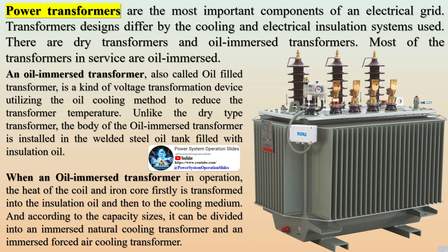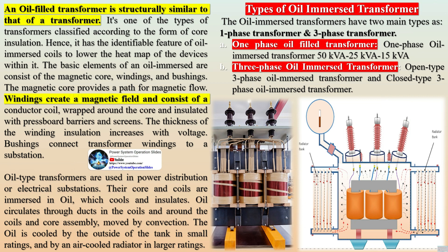An oil-immersed transformer, also called an oil-filled transformer, is a kind of voltage transformation device utilizing the oil cooling method to reduce the transformer temperature. Unlike the dry-type transformer, the body of the oil-immersed transformer is installed in a welded steel oil tank filled with insulation oil. When an oil-immersed transformer is in operation, the heat of the coil and iron core is first transferred into the insulation oil and then to the cooling medium. According to capacity sizes, it can be divided into an immersed natural cooling transformer and an immersed forced air cooling transformer.